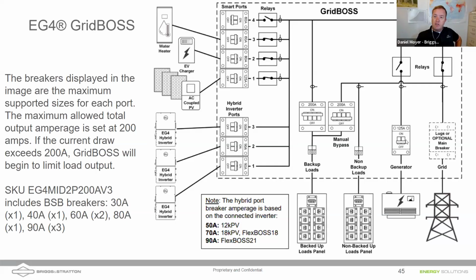The GridBOSS has a 125 amp generator input, so that's 30,000 watts coming in. Another value add is that we have a manual bypass, so if for whatever reason the whole system goes down, we can manually bypass the GridBOSS and those FlexBOSSes, and bring the grid directly down into our backed up loads as well.